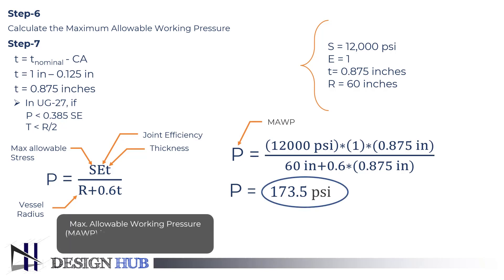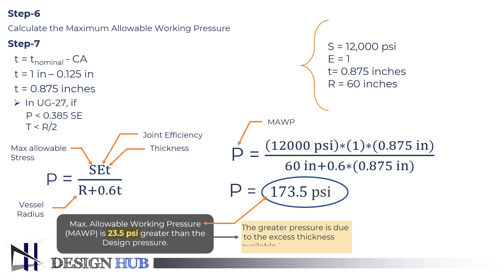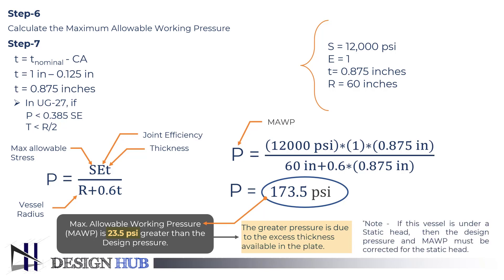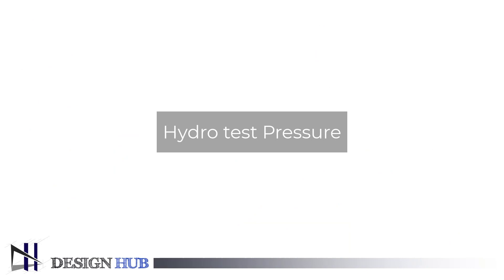This is 23.5 pounds per square inch greater than the design pressure. We are getting a greater pressure due to the excess thickness of the plate. There is one thing to note: a vessel under a static head leads to a change in design and maximum allowable working pressure. That is all about maximum allowable working pressure. We will discuss hydro test pressure in the next video.